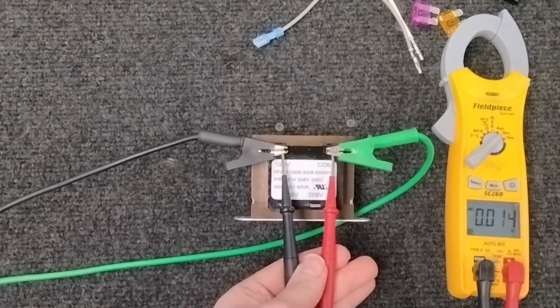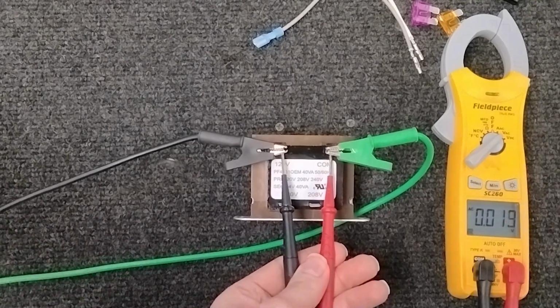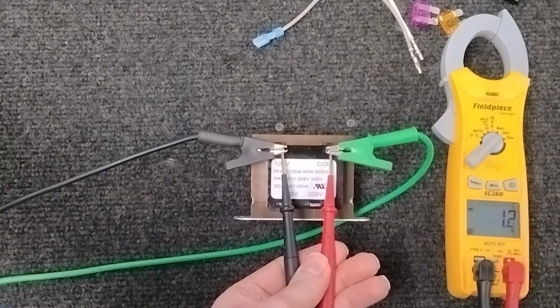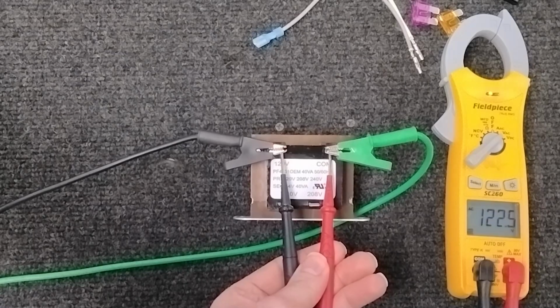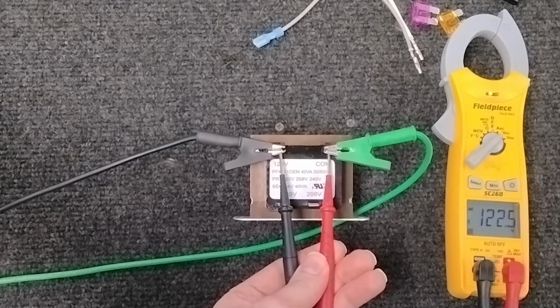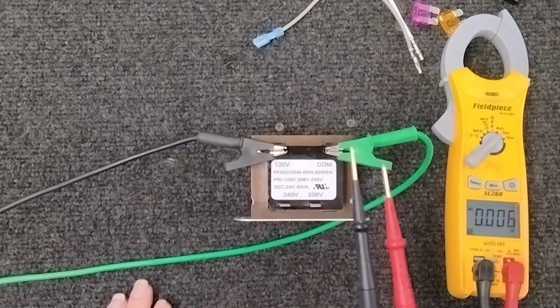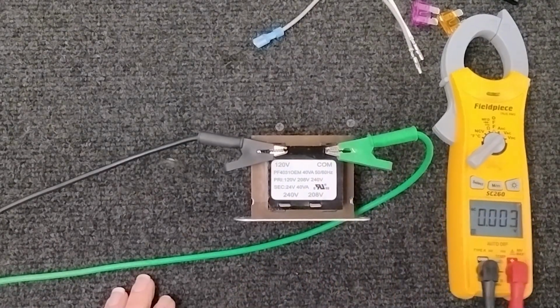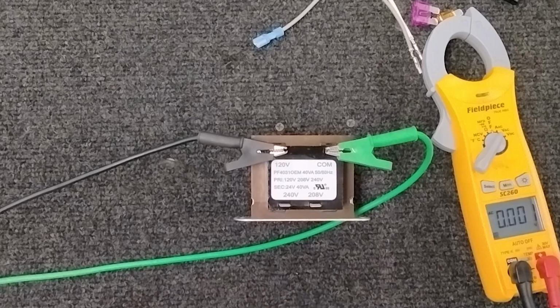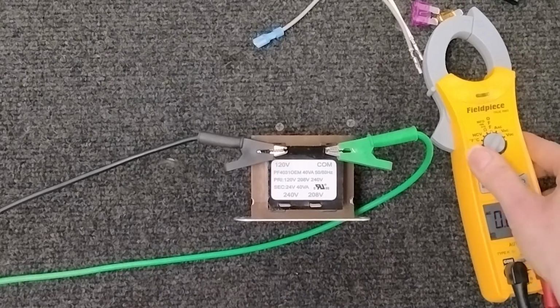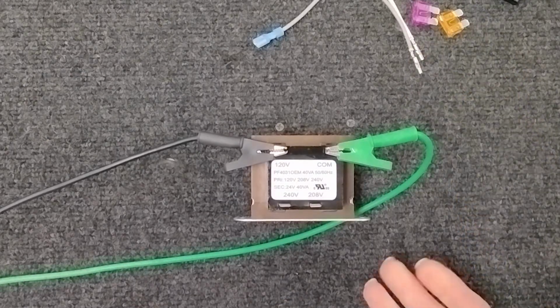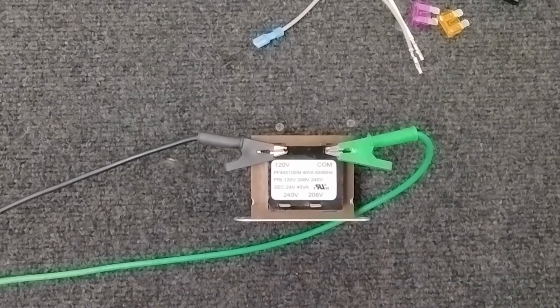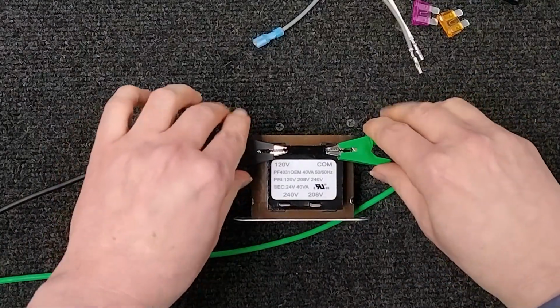All right, let me get my guys here. There we go. Like we mentioned earlier, we should be getting somewhere between 122 to 123 volts AC. So now you know you're getting power, or you're not getting power. So if you're not reading that 120 volts, you now know what the issue could be. At least one of those.